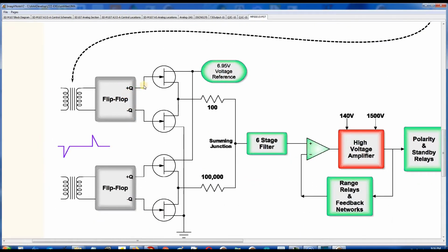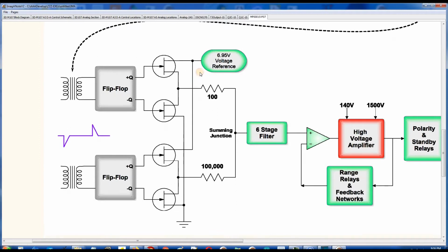Now this flip-flop drives 2 field effect transistors which act as gates to alternately connect the voltage reference, which comes from an LM299, 6.95 volts. It connects that to this point here, and in the other part of the cycle, when it's low, it connects it to ground. So this point here is going up and down between 0 volts and 6.95 volts with a duty cycle equal to the number that's been typed in to the front panel. So therefore the average value of that pulse would be 6.95 times the value on the front panel divided by 1000.